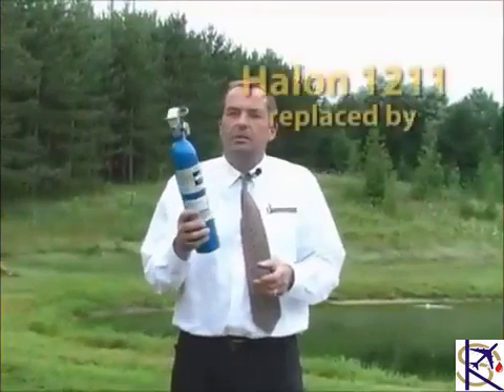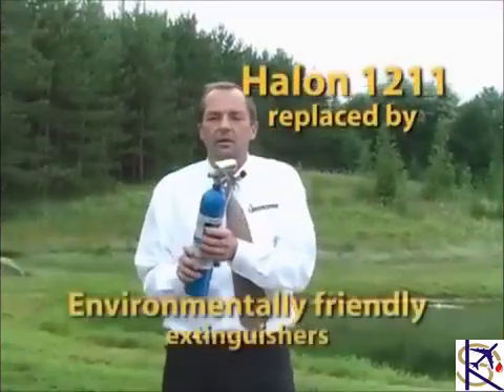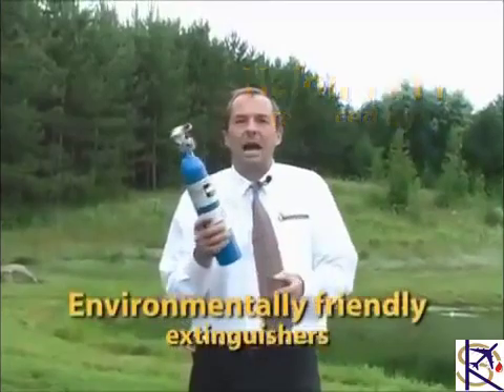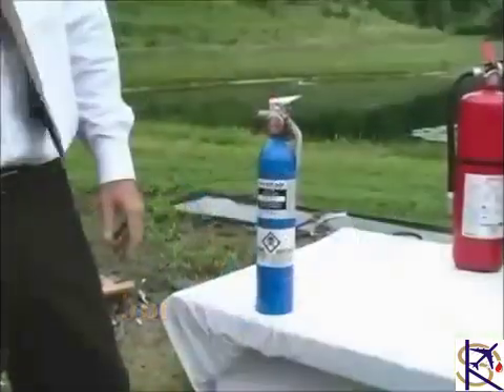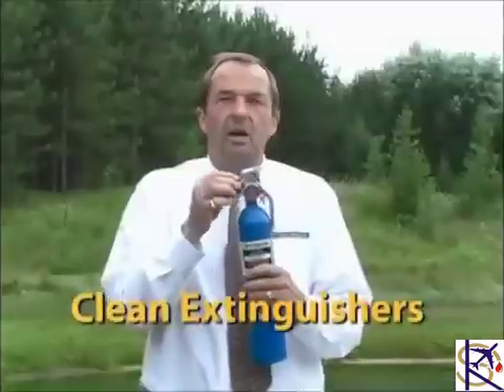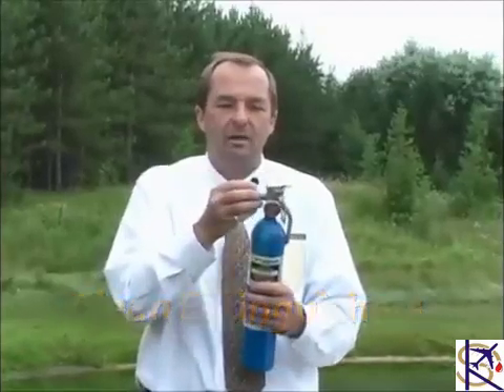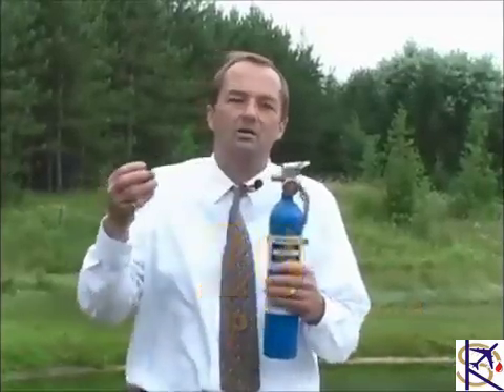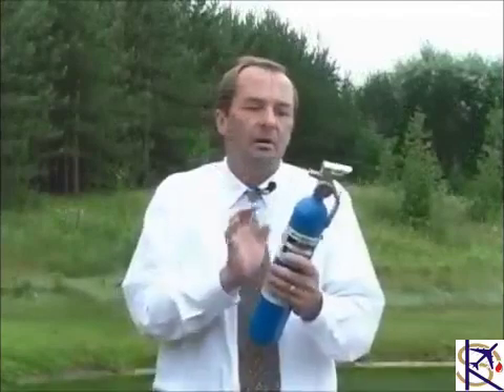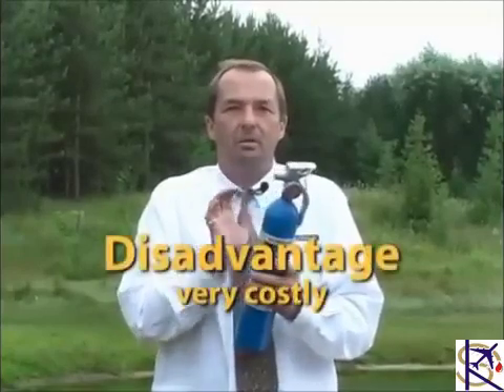This is a Halon 1211 extinguisher. These extinguishers have been replaced with new clean brand names such as Halotron. It is a Freon type of gas, roughly 20 psi coming out of the nozzle. It is cold, it turns into a gas, and it is a chemical reaction.